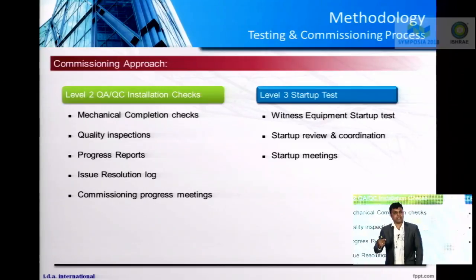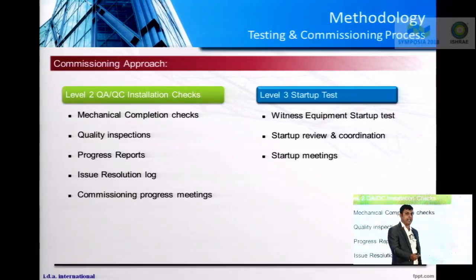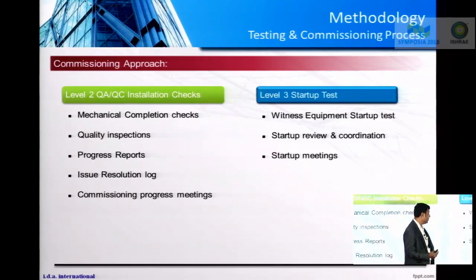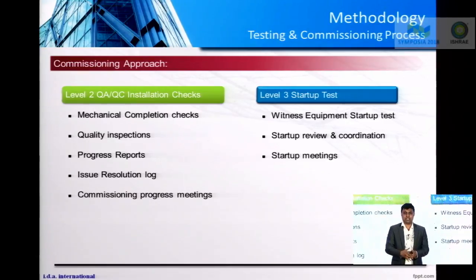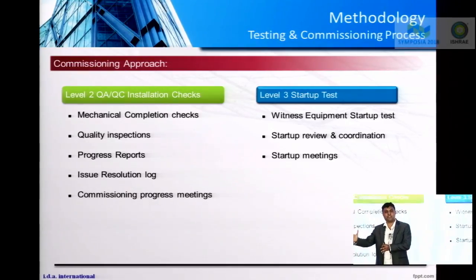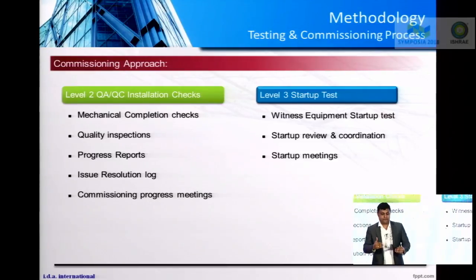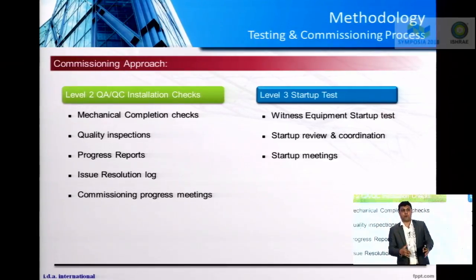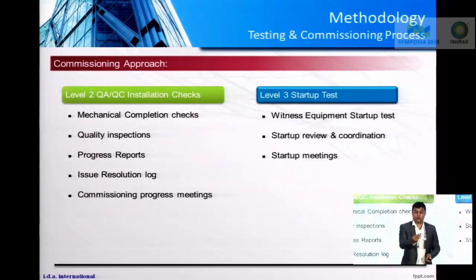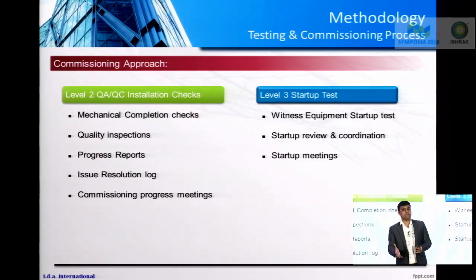It could be energizing a switchgear, energizing a CRAC unit, energizing a PDU. The startup test is a step before you start your rigorous functional testing of individual equipment. Once you energize an equipment, it is very important you do certain basic steps, follow the process or procedure laid down by the OEM, and verify certain basic parameters.